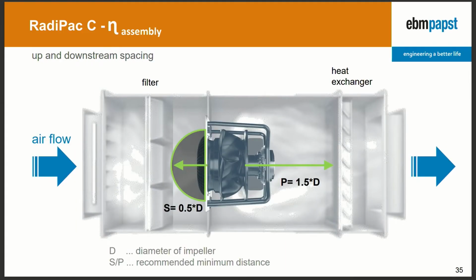So another thing to take care of is the dimensioning and positioning of the fan in the unit. On the suction side, you should have a certain space available, and also on the pressure side, especially in so-called plenum fans. The plug fans are plenum fans. They create a higher overpressure in this area, and when you have a certain distance to flaps or heat exchangers or filters, these devices get good air distribution, and so the efficiency of these units can also be increased.